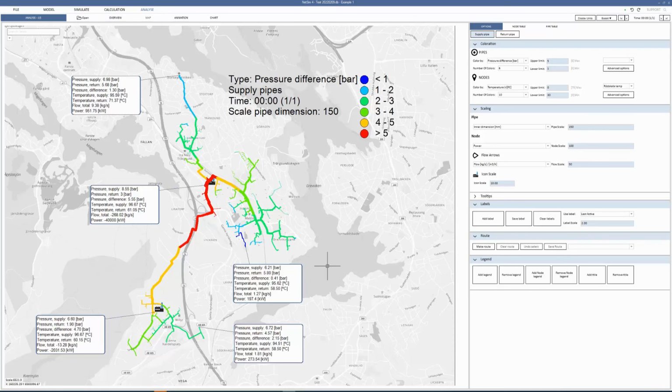We have two production plants in this case. And in this grid, we don't have any external pumping, which of course can be added as well, but in this case, we only have the distribution pumps from these two production plants going. And we have 300 consumers connected in this grid. So as you can see, the total production here is 40 megawatts in the northern plant, and then we have our secondary plant for roughly 2 megawatts of production power, as you can see in the bottom here.